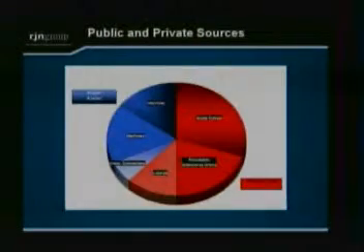This is typically, in Northern Illinois, the percentage of that clear water flow getting into the system and where it's coming from. You can see here that about 60% of it is actually coming from the private sector, which is the items in red: the laterals, some pumps directly connected, area drains, other sources. About 60% of flow, and about 40% is the public system, the main lines, the manholes, and so forth. So that is something to be aware of going forward as you're working on these systems: where is that flow coming from.